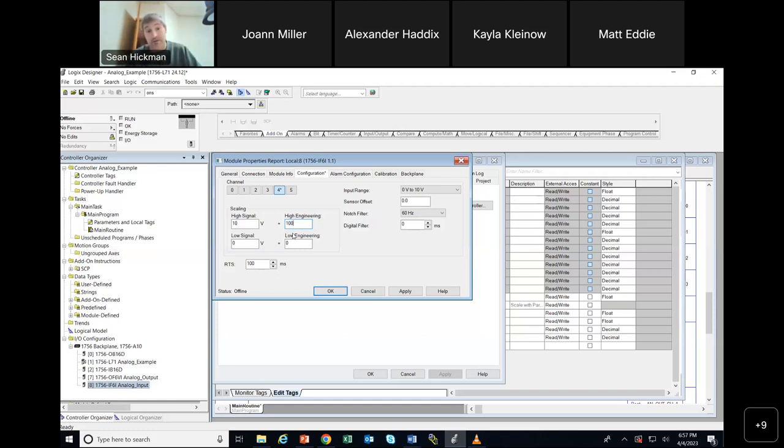Like, well, what do we need a card for? That's really dumb. Well, let's say this read from 2 to 7.5 volts, and it was giving me an engineering range of 16.5 to 234.5. So now I ask you, what is 4.63 volts? Everybody, what's the answer there? Well, I don't know, I do a little math on that. Yeah, you do have to do a little math. It's setting up an equation to equate the slope of this line to the slope of this line. The card automatically does it for you.